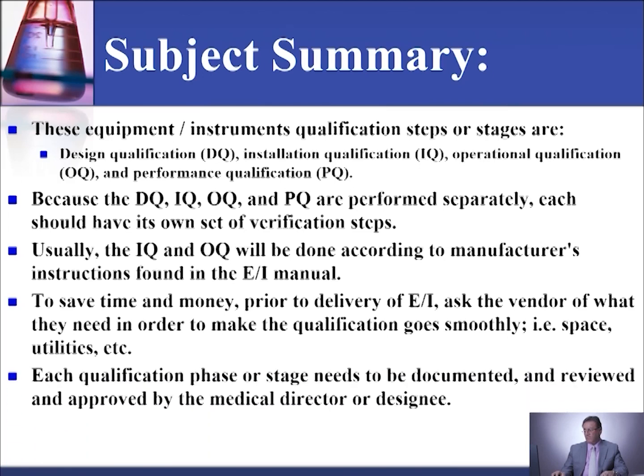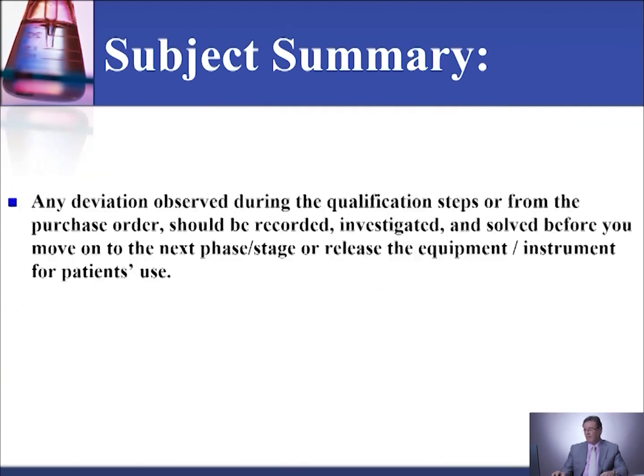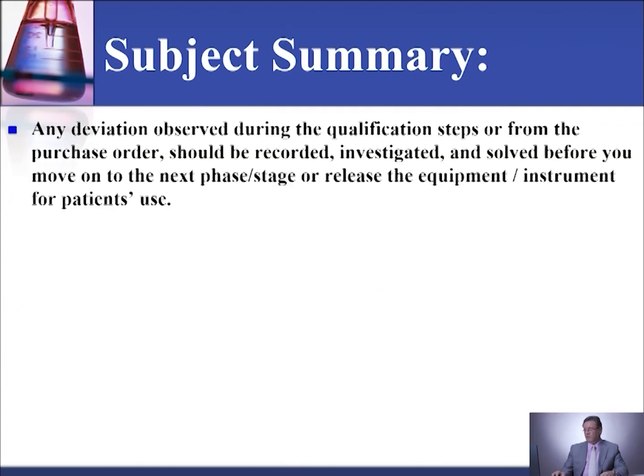Each qualification phase or stage needs to be documented, reviewed, and approved by the medical director or designee. Documents need to be kept for how long? They need to be kept as long as you keep that equipment or instrument, plus 2 more years per CAP, 3 more years per CBAHI, that's for the general lab, and 5 years for a blood bank. Any deviation observed during the qualification steps or from the purchase order should be recorded, investigated, and resolved before you move on to the next phase or stage or release the equipment or instrument for patient use.